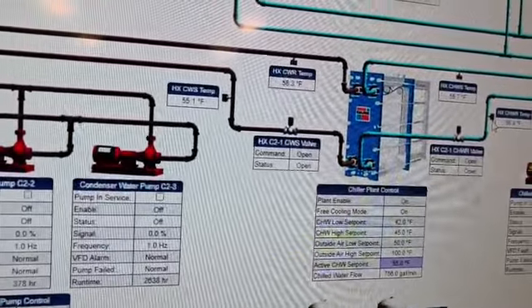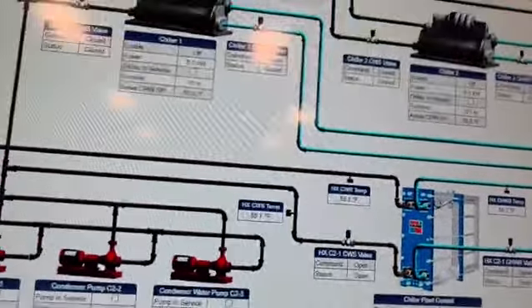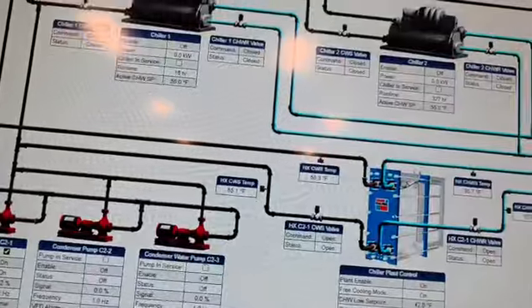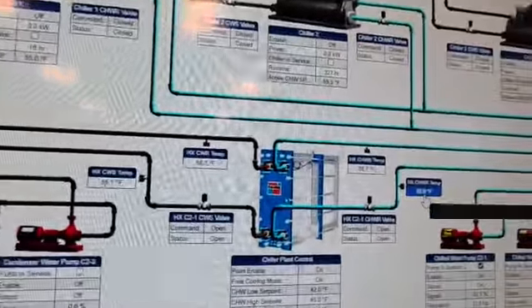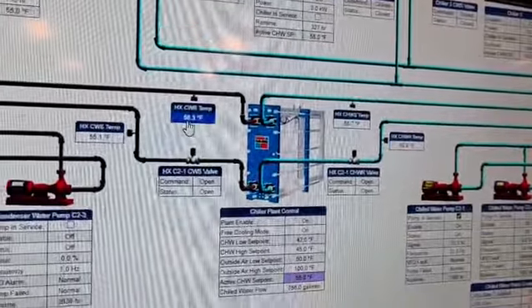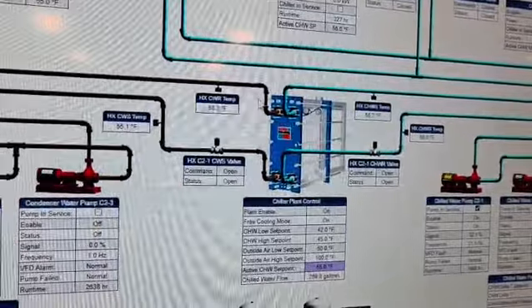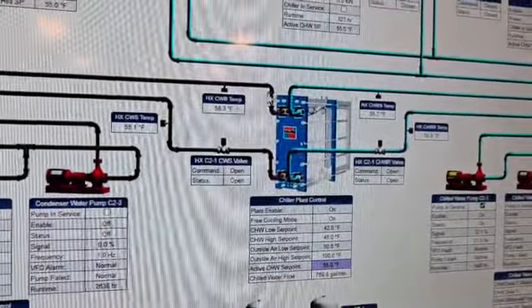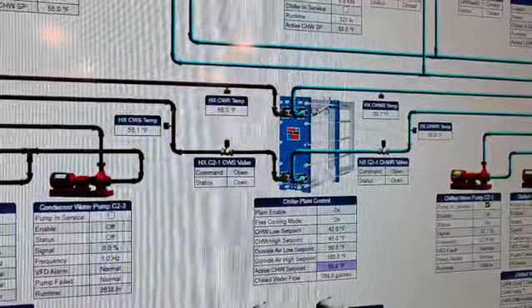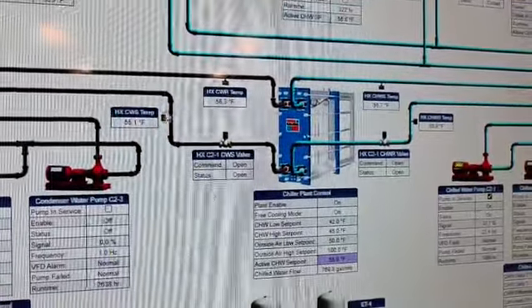You need to understand where the water is going. Sorry, this is coming from the building, 58.9, and it's exchanging to 58.3. It's almost the same temperature. This one gets hot, goes back to the cooling tower, cools down, and comes back at the end.